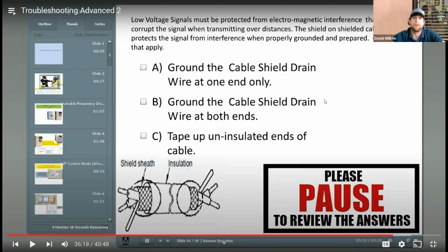We're supposed to ground your shielded cable at one end only or at both ends? I believe you do it at both ends. No, one end only. One end only. You're trying to drain the signal off. If you connect it on both ends, it sets up what they call a ground loop. Ground loops are extremely hard to find in the field.